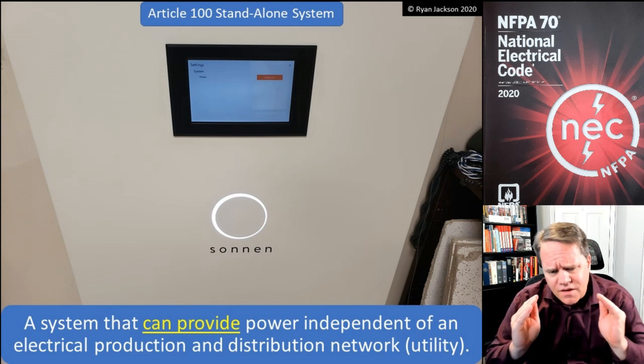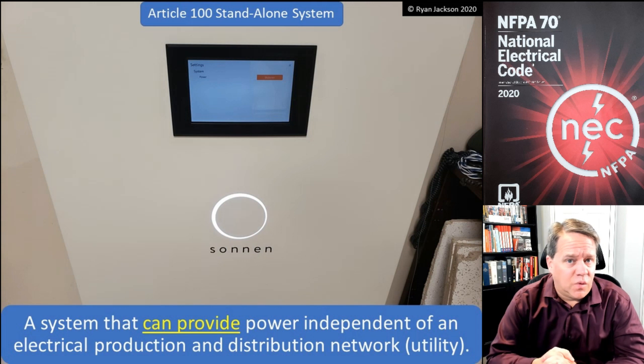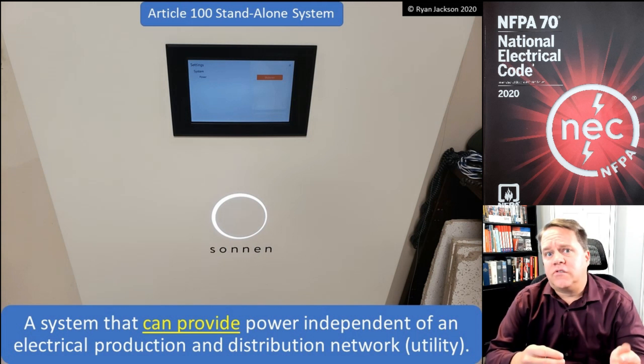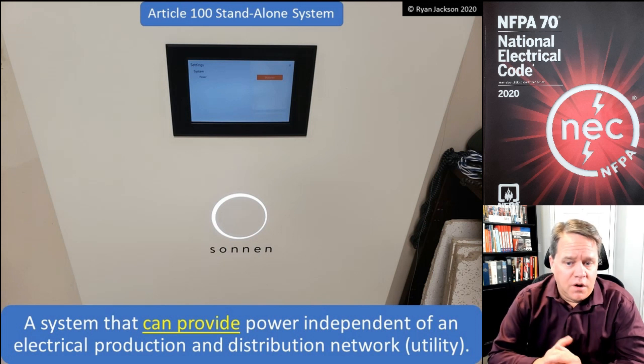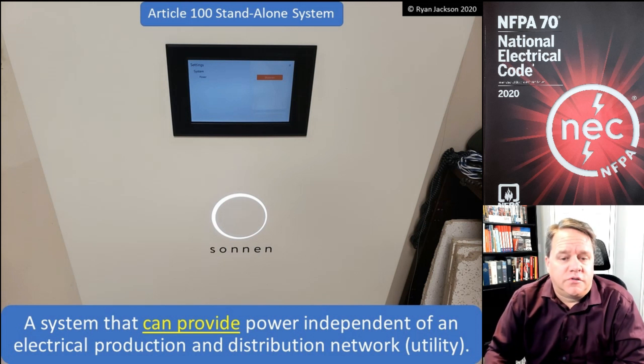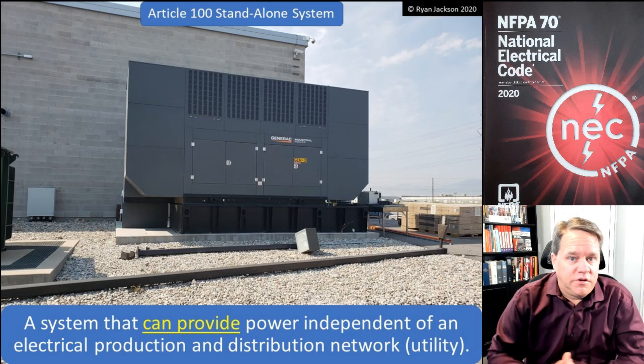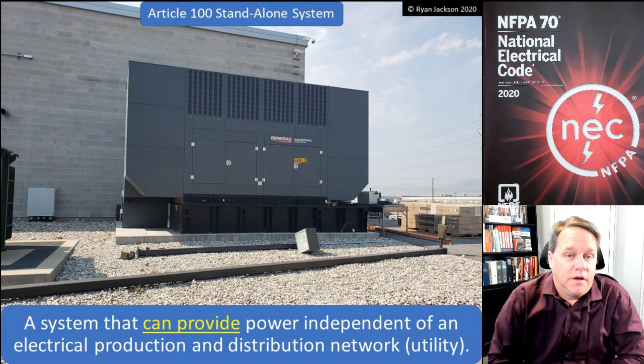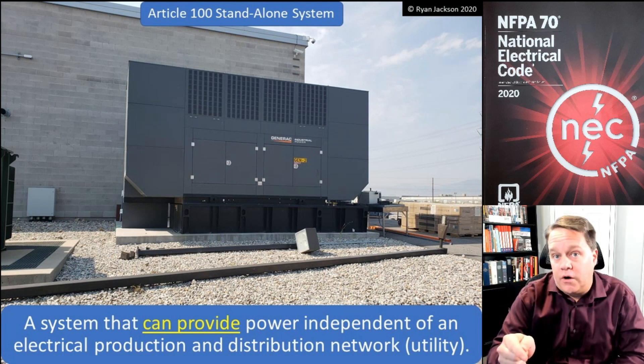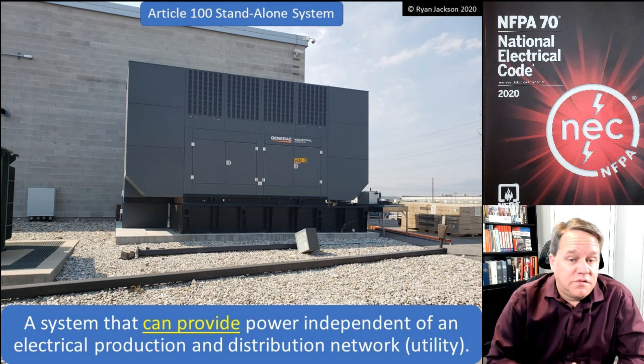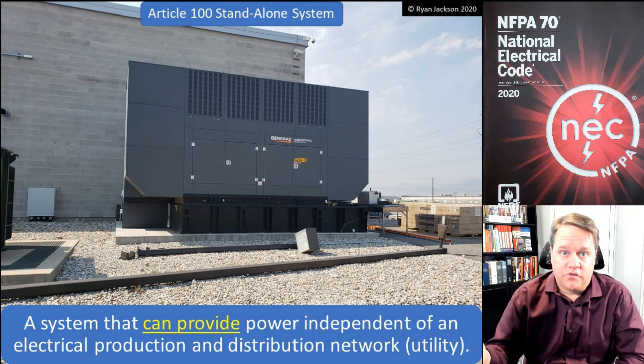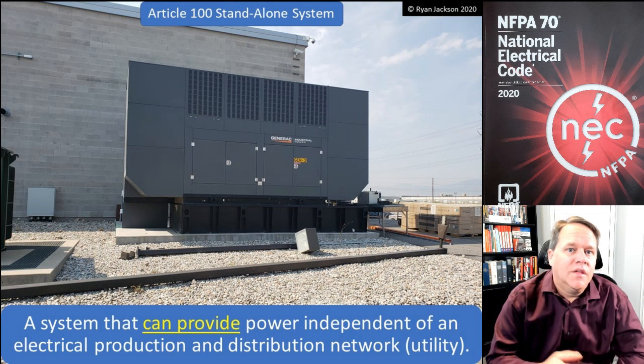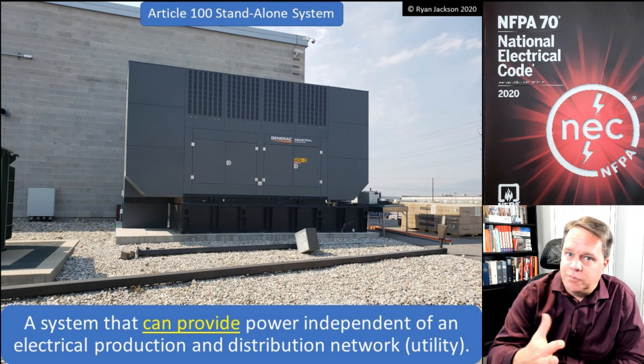The standalone system definition was tweaked in the 2020 version of the NEC. It says it's a system that can provide power independent of an electrical production and distribution network, which would be a utility. Well, any generator meets that definition — can a generator provide power that's independent of a utility? Of course it doesn't need the utility to function. So the definition of a standalone system isn't perfect.